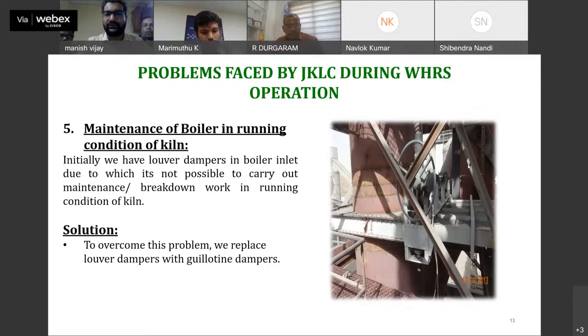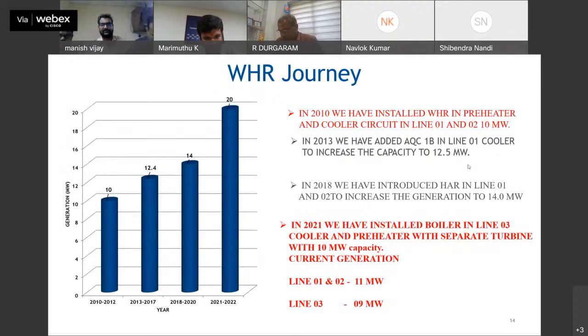It is very tough to do the maintenance of the damper during the running conditions, as we had louver dampers earlier, and we were continuously facing problems in the damper for leakages, internal as well as external. So our team decided to replace these dampers with guillotine dampers. By doing this, we were able to sustain our generation continuously. Now I would like to call my colleague for further explanation.